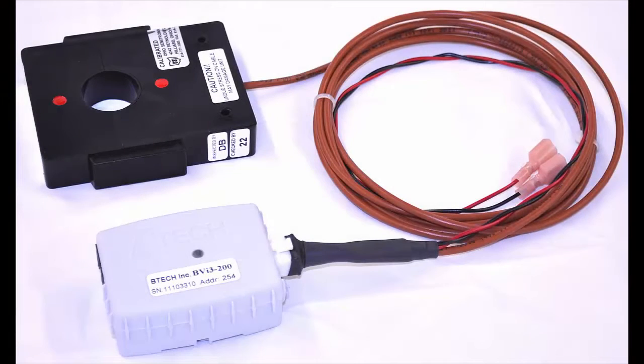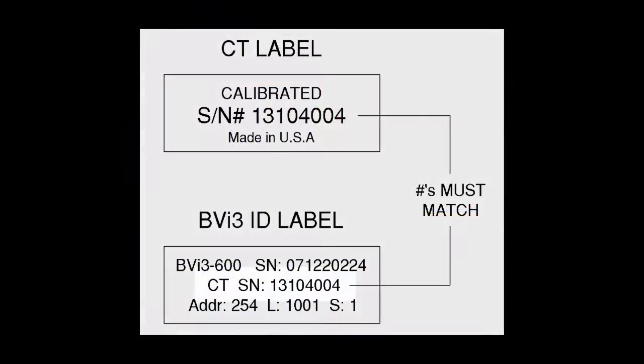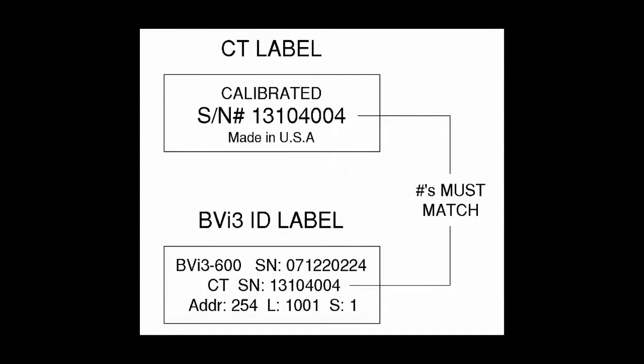For most CellQ1 systems used on GenSets, string current monitoring is not required. But if your system does, then the BVI3 and current transducer need to be installed. First, verify that the BVI3 serial number matches the CT serial number. These modules are calibrated together and are not compatible with mismatched CTs.